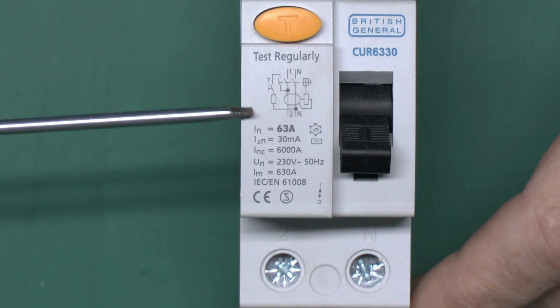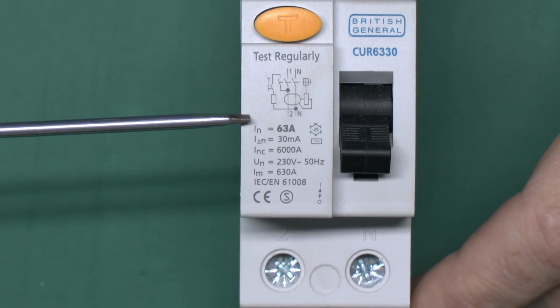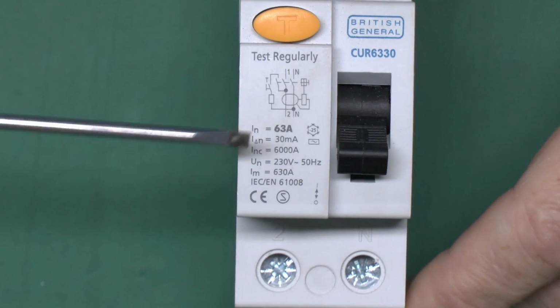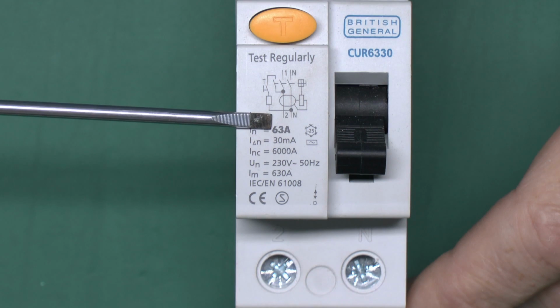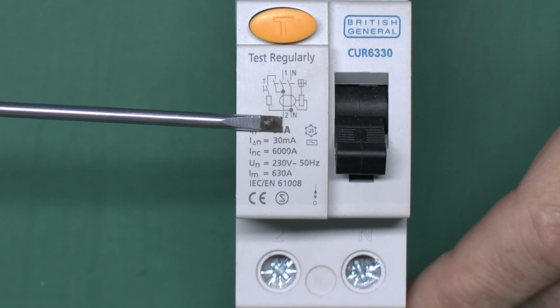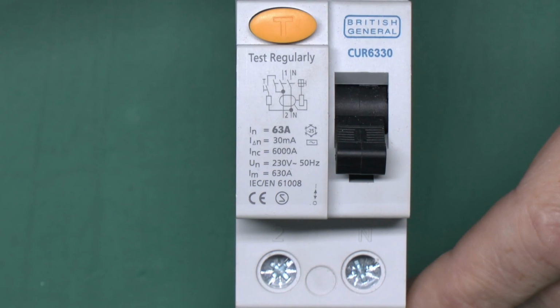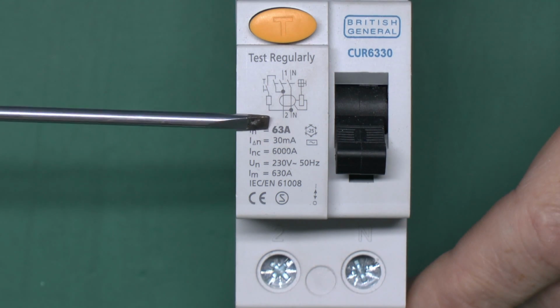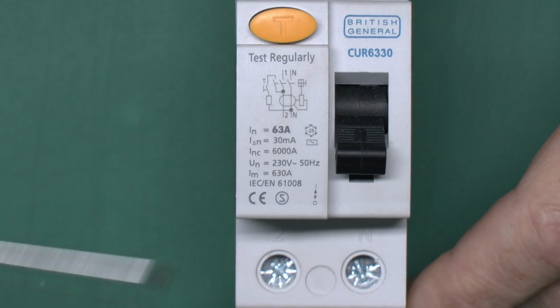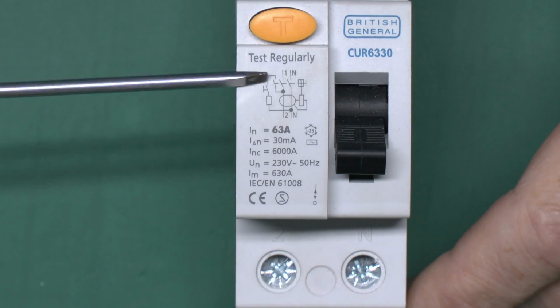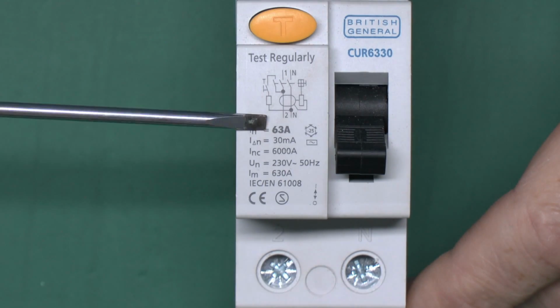Now it's important to note that these devices do not react to overloads or short circuits. Most of them will have a rating on the front here, in this case 63 amps, but that's just a rating of the internal contacts and switching mechanism. That does not mean it's going to suddenly trip out when you exceed 63 amps. You could put 200 amps through this device, it won't trip or do anything. Again, if you shorted out the supply and several thousand amps flowed through it, again it's not going to disconnect at all. That's purely there as a maximum rating of equipment you can connect downstream of it.